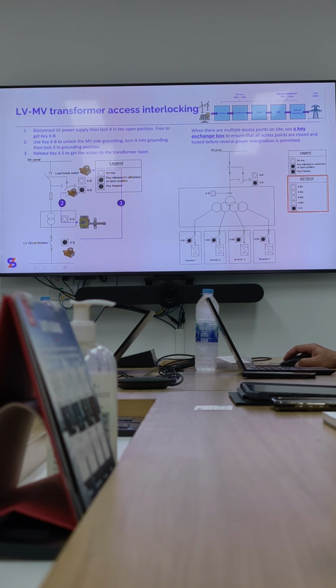Then from here we again isolate the MV side, and take out this key. So now LV is isolated and locked, MV is isolated and also locked, and the key goes into the transformer cabinet or transformer room, so upstream and downstream are isolated and safe.